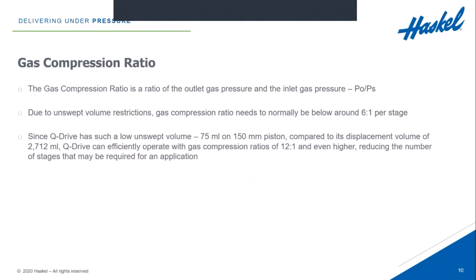The Q-Drive, as mentioned, has a very low unswept volume. On our 150 mm piston, the unswept volume is only 75 milliliters, while the actual displacement of that piston is 2,712 milliliters. So we have a very small unswept volume compared to the actual displacement. Because of that, the Q-Drive allows gas compression ratios of 12 to one and even higher. With higher gas compression ratios allowed, we can get away with fewer stages, which means less hardware is required to get gas from a low pressure to a very high pressure.